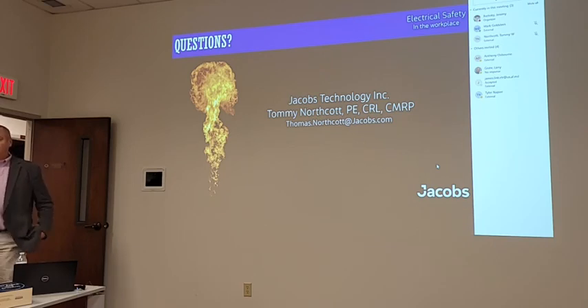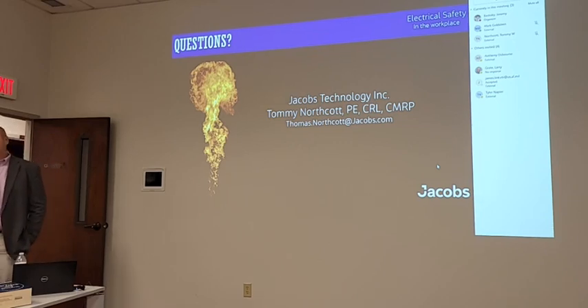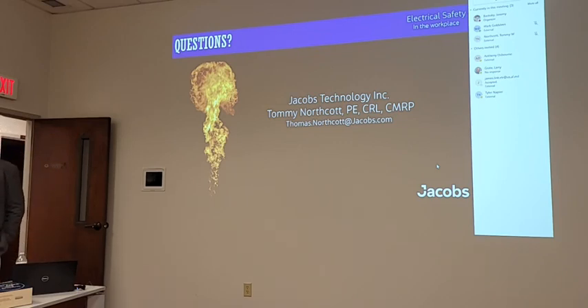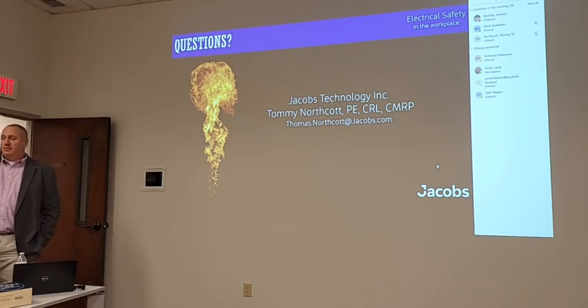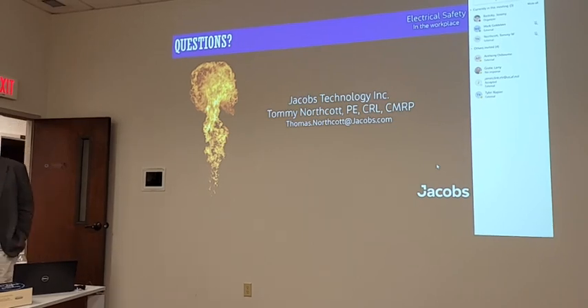So if it's not arc rated, that'd be the first question. If you're going into a facility, the first question is: is this arc rated gear? If it's not arc rated gear, then you can't assume that it's going to contain the arc when it happens. And if that's the case, then whatever you're operating, the next question is, where is the contact making or breaking, and am I inside or outside of that arc flash boundary? If you're outside the boundary, then yeah, you can operate it without the PPE. If you're inside the boundary, you have to have PPE on, even if all the doors are closed and latched.